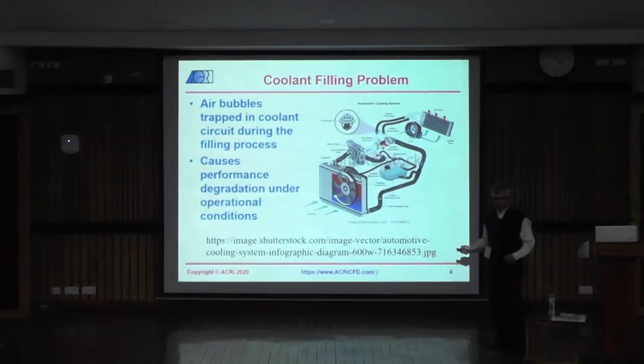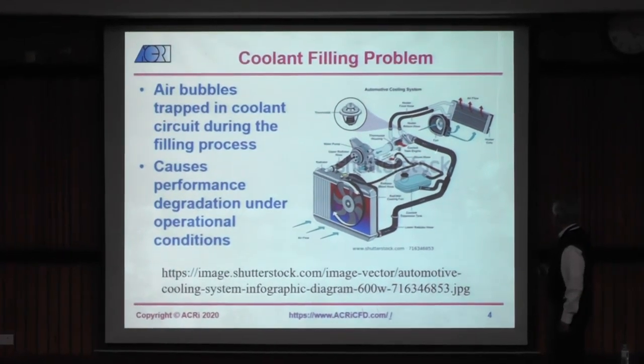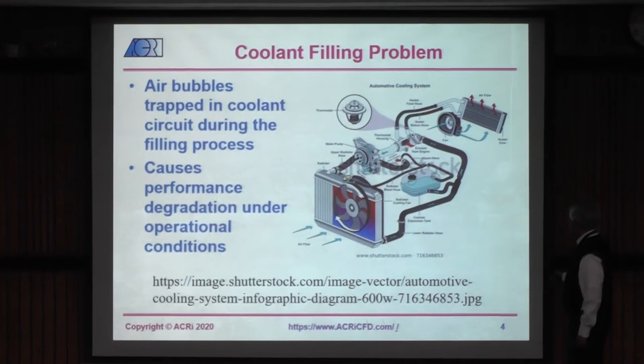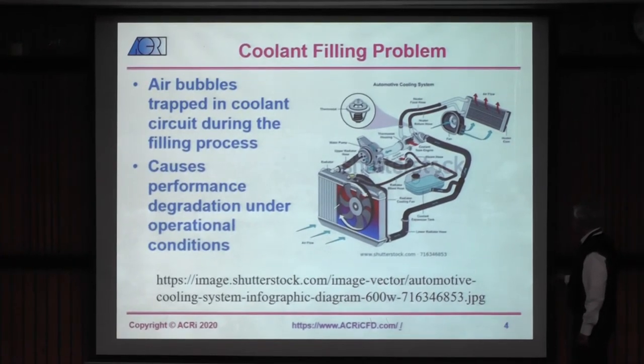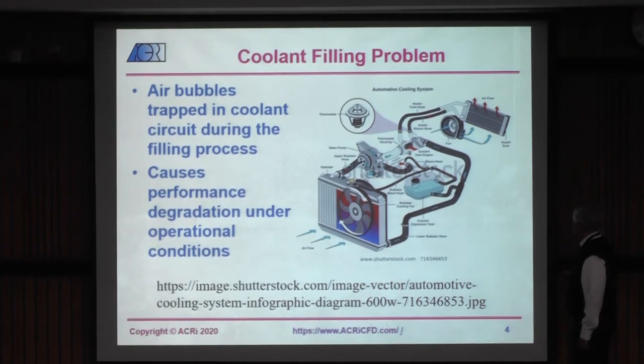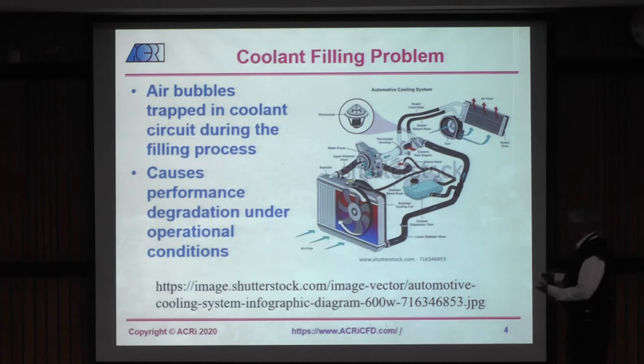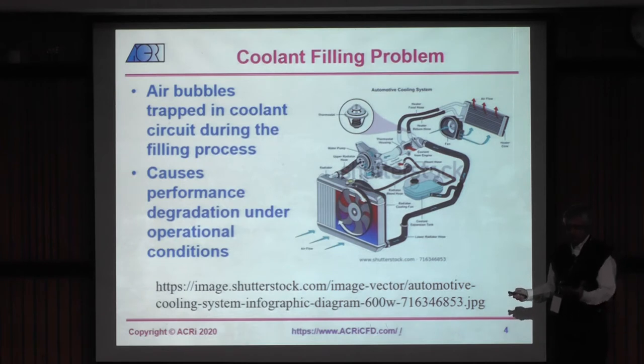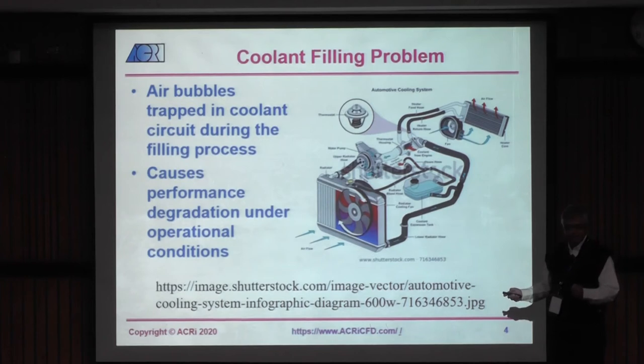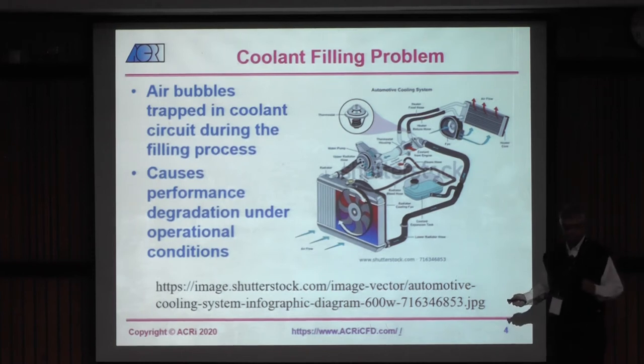These air bubbles spread through the system during operation and reduce the thermal performance. The system is a fairly complex arrangement of tubes, several circuits, pumps, and radiators with many little fin tubes. When you fill it, there are air bubbles trapped in the system. We went to see the experiment being done by the client in Bangalore — after filling with coolant, they turn on the pump and the entire thing turns a milky white color because of the presence of air, which is extremely detrimental to performance.